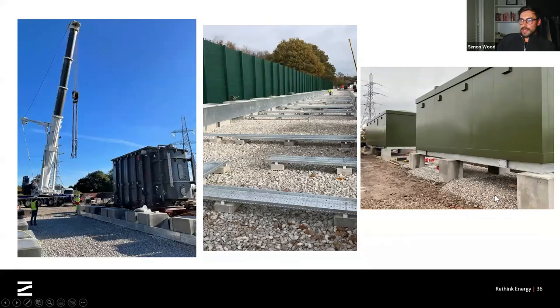These images show a couple of things. We've got the main transformer being delivered and lifted into place. This is the main tank of the transformer itself. The ancillary parts are then assembled on site before that's connected all together to the rest of the HV infrastructure. This shows all of the cable containment going in across the site. Obviously, this is now all hidden by the containers.